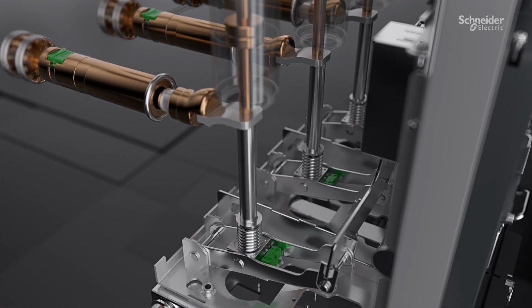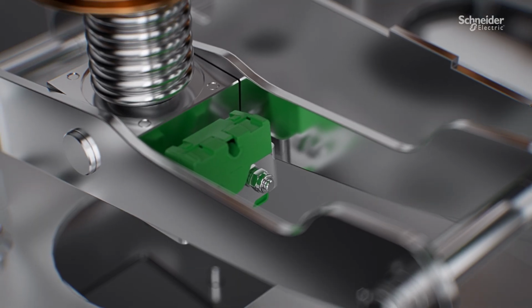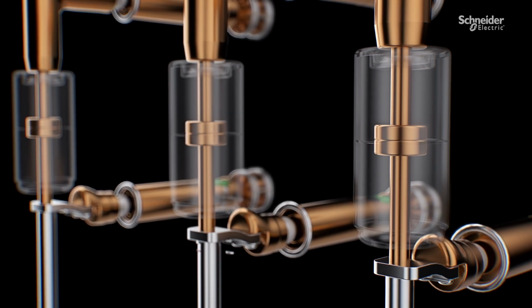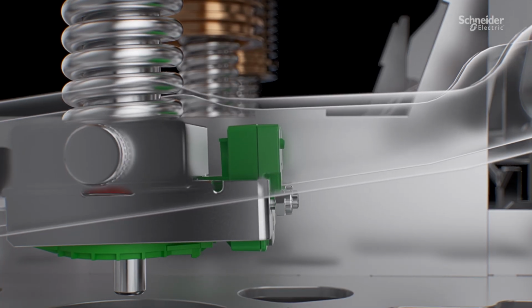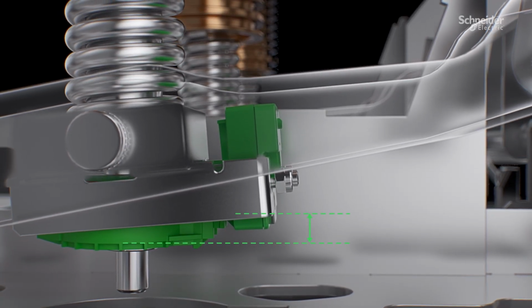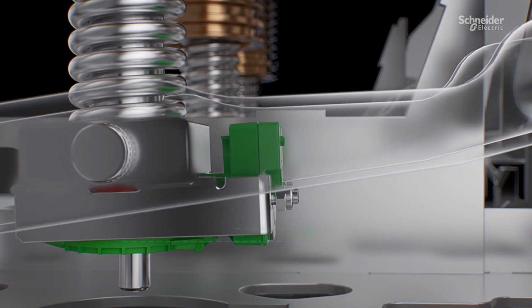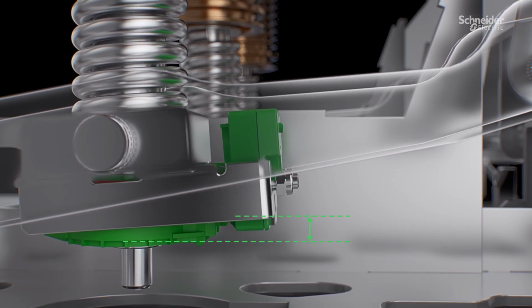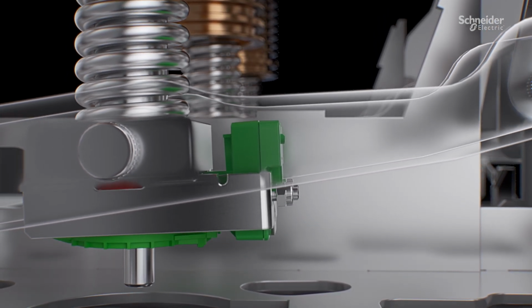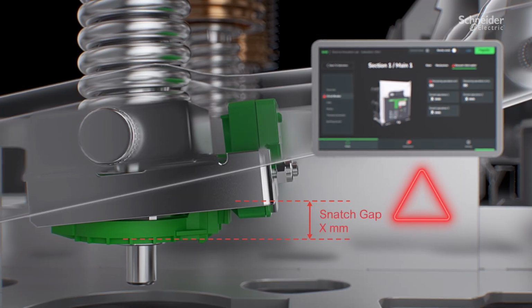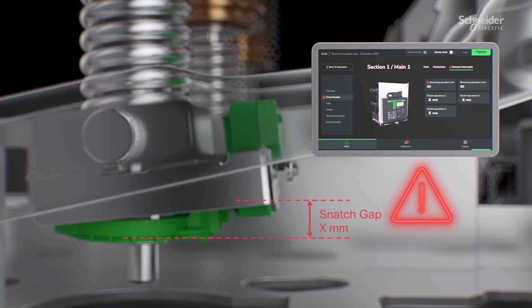Every time a breaker operates, especially under high load or fault conditions, its electrical contacts erode. This erosion is a primary health indicator. From day one, a dedicated sensor measures erosion and alerts when it becomes excessive. Measurements feed into our aging model and can be viewed in the mobile app.